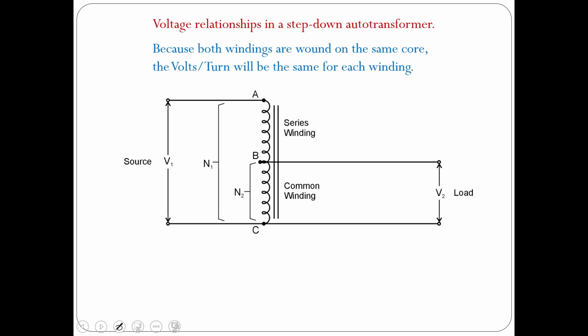And here's the voltage relationship on a step down. Once again, the volts per turn ratio is going to be the same. So here's a 600 volt source, and the total turns of both the series and the common winding combined is 2400. So our volts per turn would be 600 divided by 2400 turns. That would come to 0.25 volts for every 1 turn.